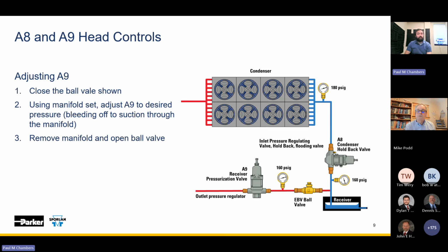To that point, like you said, you can do them in parallel, but with the ORD, you could also do them in series, right? So if I had two 20s and I put them in line, you would have a 40. Yes. In parallel, you don't increase the setting, you increase the volume. In series, you increase the setting. So two 20s in series, you would have a 40. If for whatever reason you did need a 40, which is odd, but it might be required.